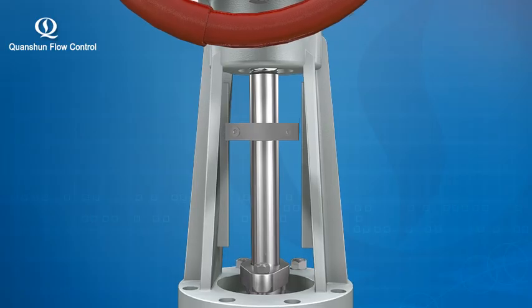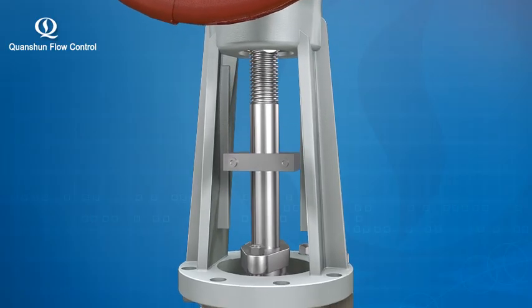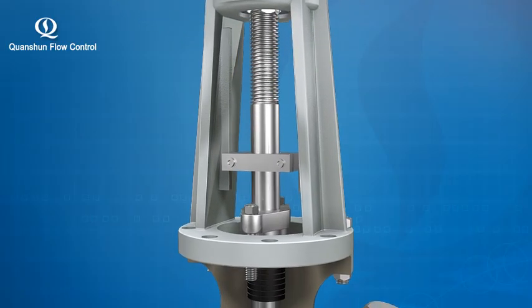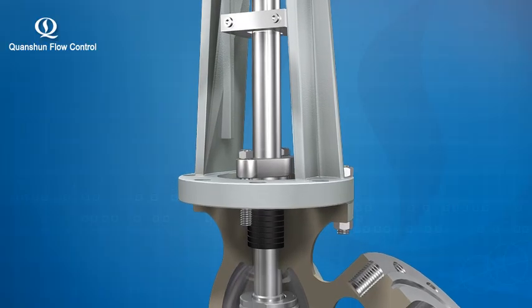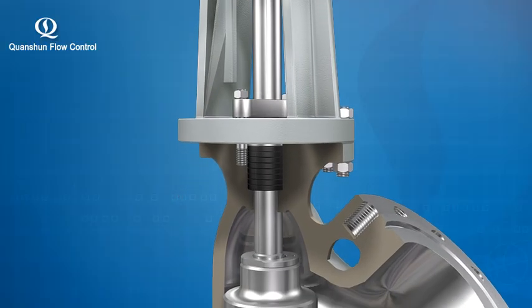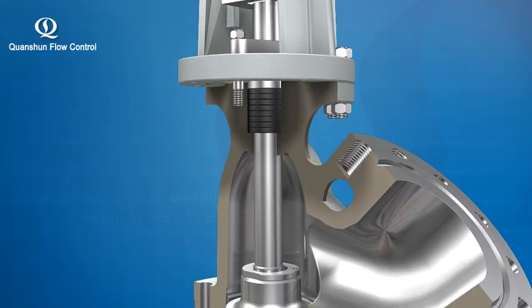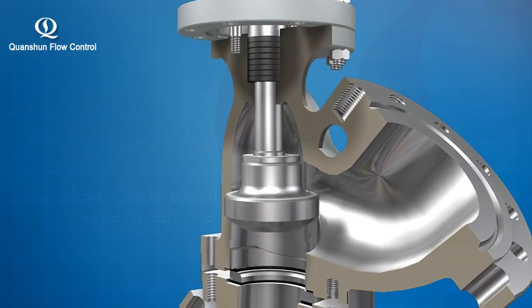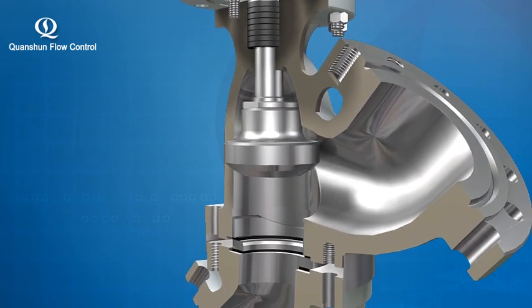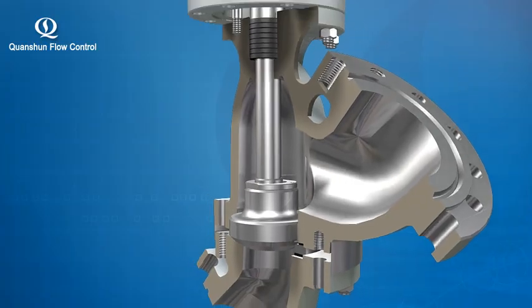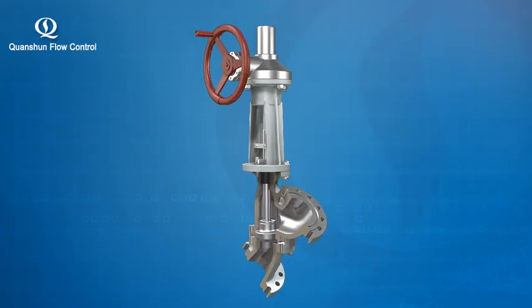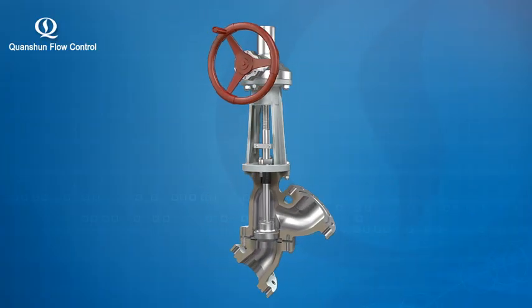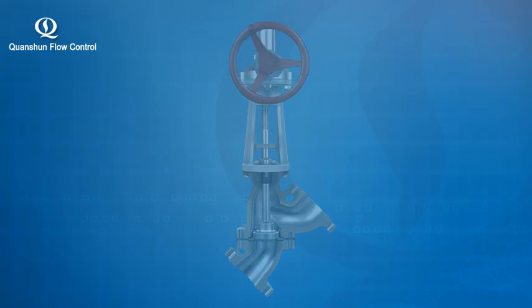5. The use of anti-rotation mechanism on the stem keeps the stem moving linearly up and down, based upon the fluid characteristics of materials used in alumina plant. The upper flare design ensures the seal face is less likely to be scabbed and guarantees the seal effect required. The special valve design allows the stem to run at no load, even when the valve is scabbed, for the purpose of improving valve operating safety and prolonging its service life.